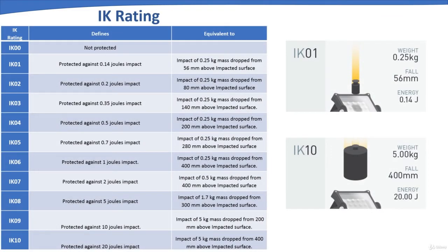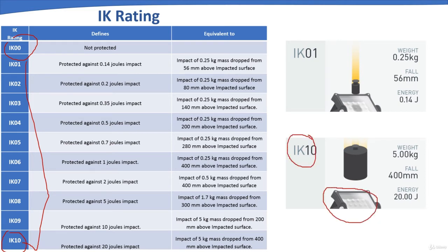IK rating is the degree of protection provided by enclosures against external mechanical impacts. The IK rating scale runs from IK00 up to IK10, as shown in the table. For example, an object with a rating of IK10 means that a foreign object weighing 5kg falling from 400mm with an energy of 20 joules will still not cause damage — the object can withstand this mechanical impact and will be protected.